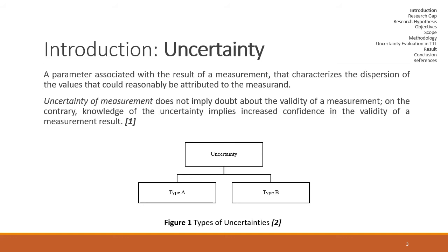On the contrary, Type B uncertainty is estimated from any other information. This could be information from past experience of the measurements, from calibration certificates, manufacturer's specifications, from calculations, from published information, and from common sense. Type B evaluation of uncertainty is one carried out by means other than the statistical analysis of a series of observations or measurements. Therefore, it cannot be reduced by increasing the number of measurements if the equipment and conditions of the measurements remain unchanged. It includes information such as previous measurement data, experience with or general knowledge of the behavior and properties of relevant materials and instruments, manufacturer's specifications, and data provided in calibration and other certificates.